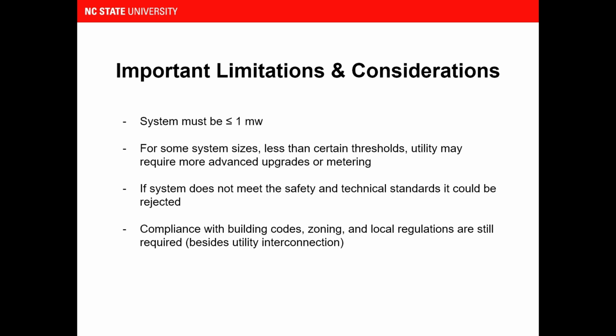Some important limitations and considerations that clients should be aware of are, firstly, the system must be 1 megawatt or less. Systems above that size are subject to a different regulatory framework. Secondly, depending on the size and location of the system, NV Energy may require additional grid upgrades or advanced metering, especially if the project is large enough to impact the local feeder. Third, if the system doesn't meet safety or technical standards, whether it's wiring, protection equipment, or code compliance, the utility has the right to reject the application until the issues are fixed. And finally, while interconnection handles the utility side, the project still must comply with local building codes, zoning rules, and permit requirements. These are separate from utility approval and must be completed for the project to move forward.